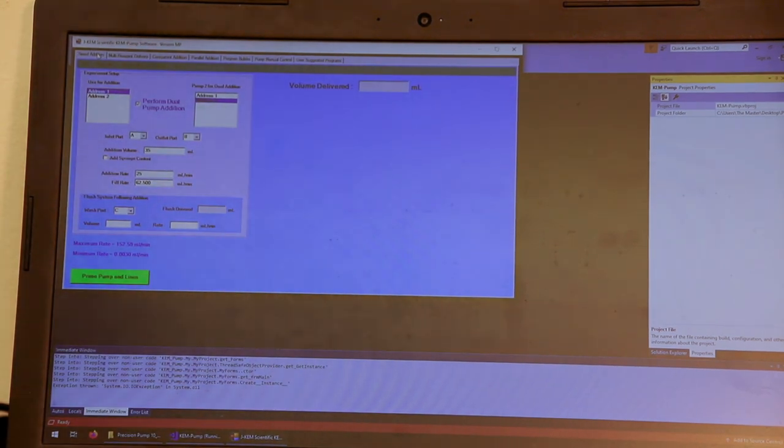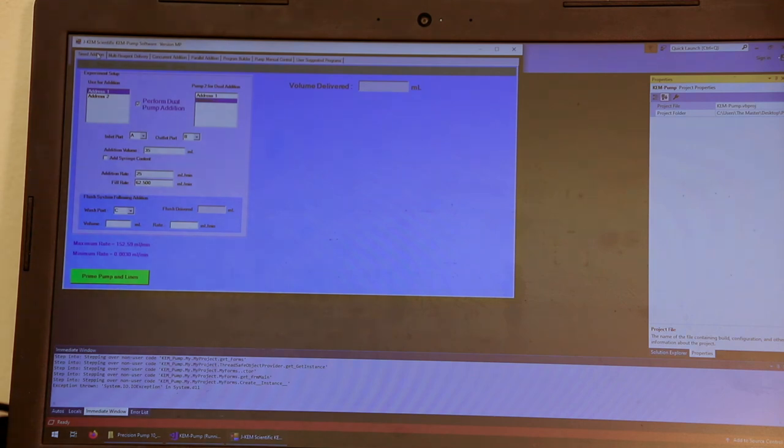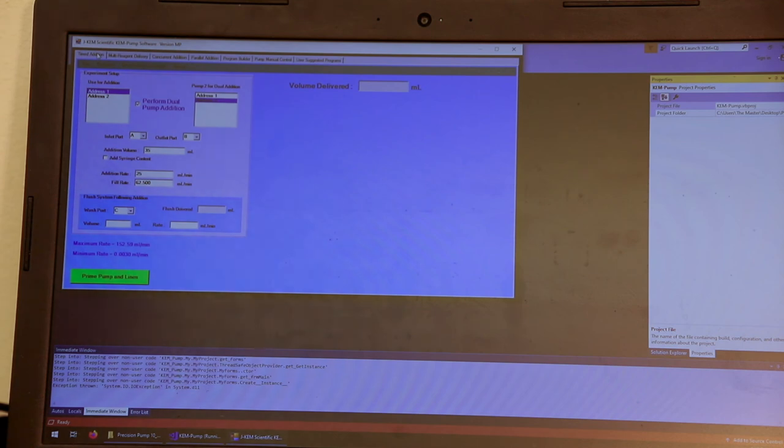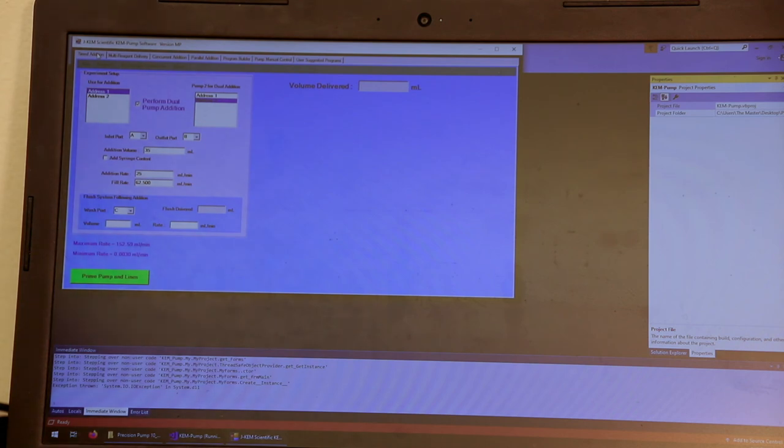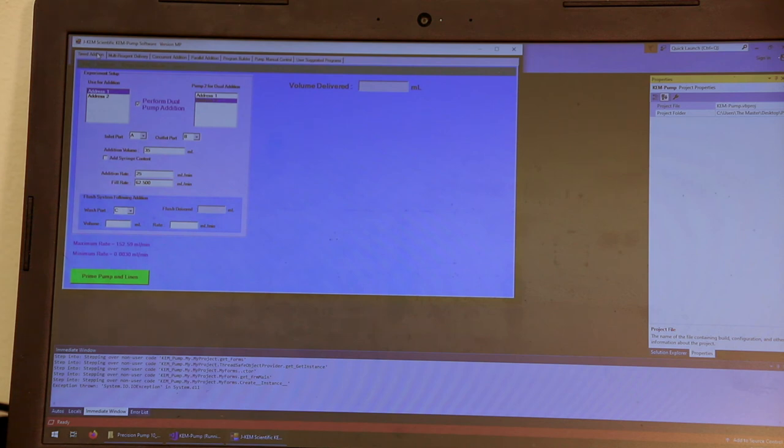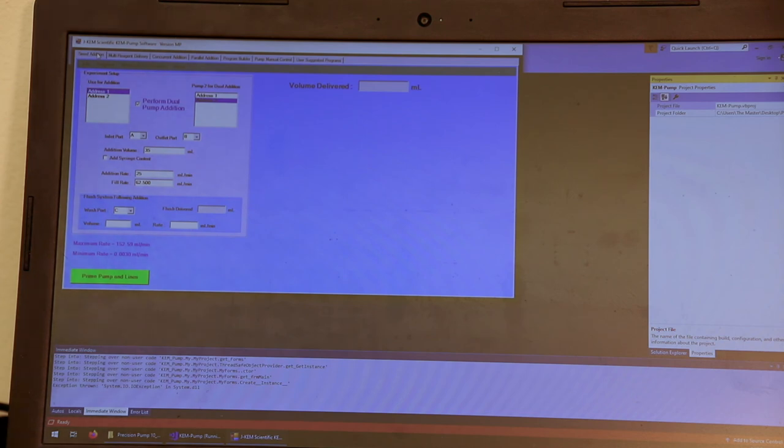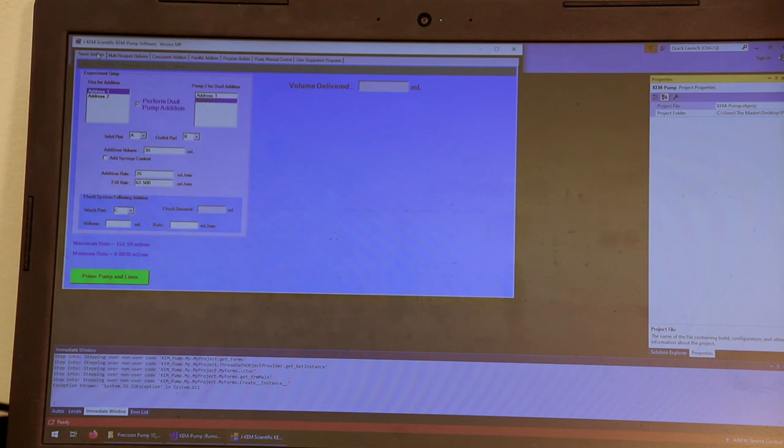J-KEM's pumps are designed to work with other pieces of J-KEM's equipment. So, for example, if right now I plugged in a J-KEM temperature controller, an image of that temperature controller would appear right here on screen. And now, since I can measure the temperature of my reaction, I can do temperature dependent additions. So, for example, I could run the other experiment I did in the very beginning and say I want you to add 50 milliliters of this reagent over the course of one hour. But if the reaction starts to go over 60 degrees centigrade, then I want you to slow the addition of the reagent. And if it actually goes to 65 degrees centigrade, I want you to stop the addition of the reagent until it cools down and then you can resume the addition. So, simply by adding a J-KEM temperature controller, now you can do temperature dependent additions.